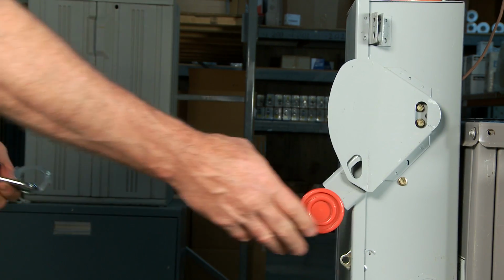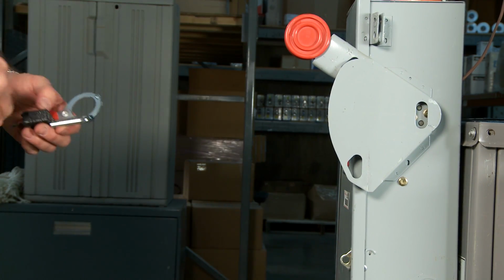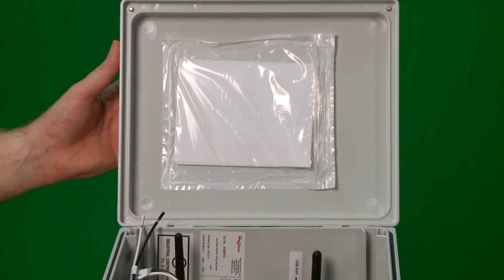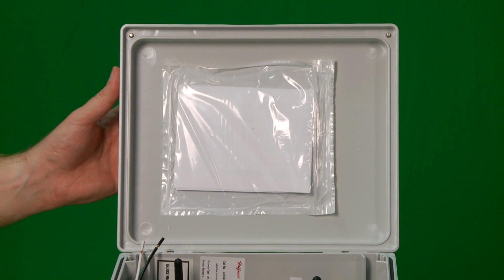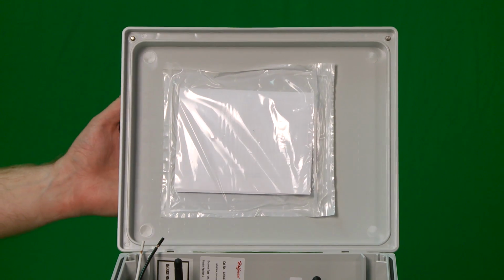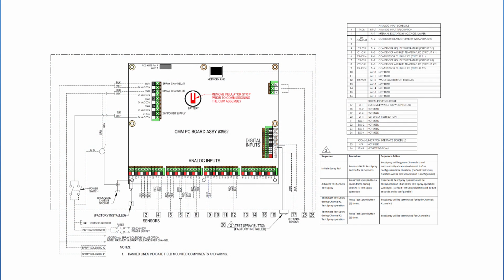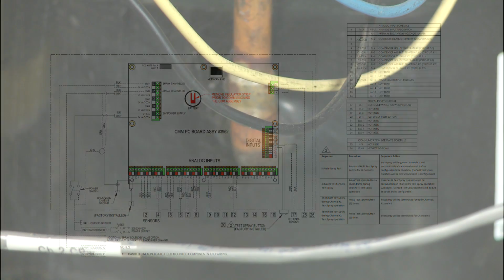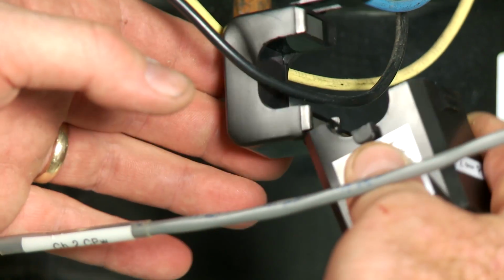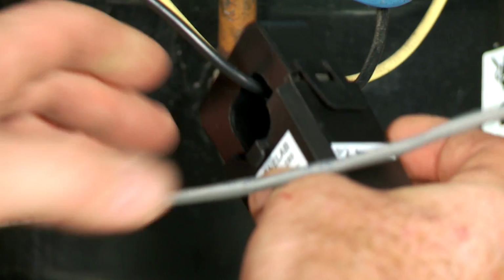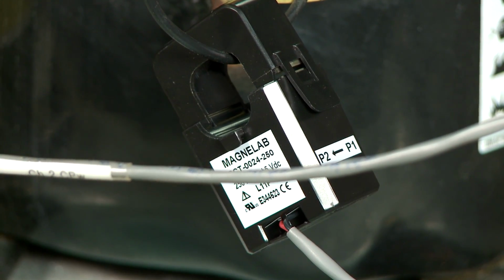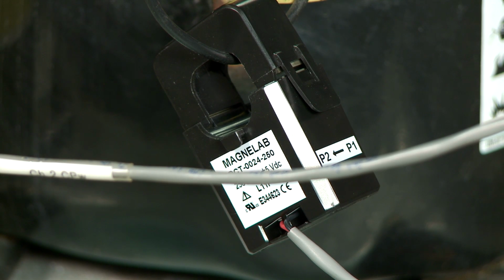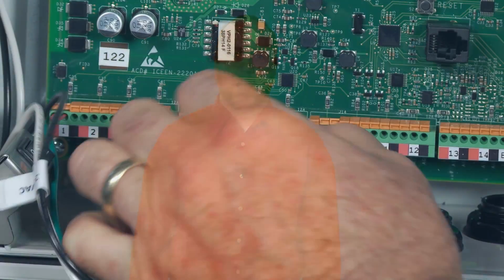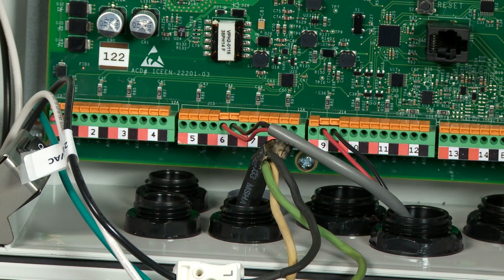The next steps involve attaching the monitoring sensors to the controller. A wiring diagram is included inside a plastic pouch on the controller lid. It is important to properly follow that wiring diagram in detail. I'll go over the basic steps for you here. First, clamp a current transducer to a phased leg of power as indicated in your customized Evaporcool system layout diagram. Connect the leads through the cable grip on the controller box, then attach to the controller board.